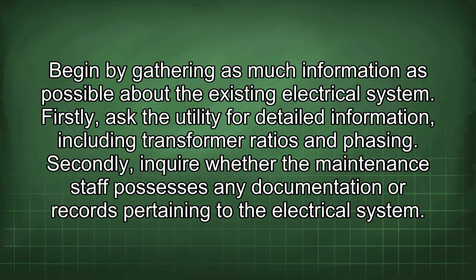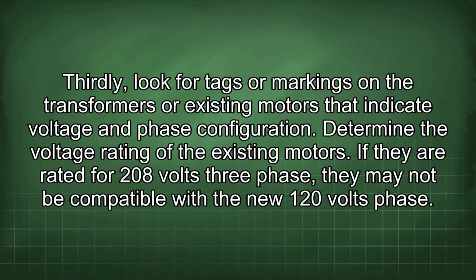Begin by gathering as much information as possible about the existing electrical system. Firstly, ask the utility for detailed information, including transformer ratios and phasing. Secondly, inquire whether the maintenance staff possesses any documentation or records pertaining to the electrical system. Thirdly, look for tags or markings on the transformers or existing motors that indicate voltage and phase configuration.